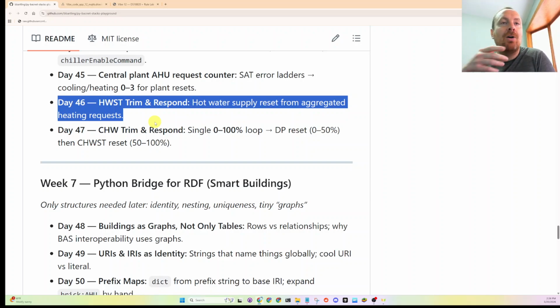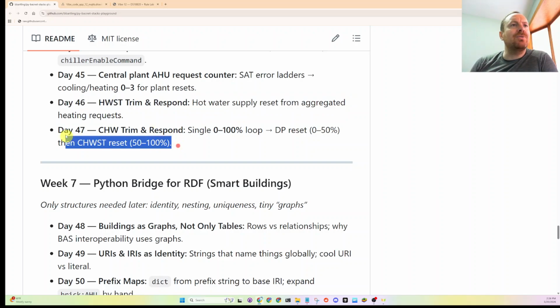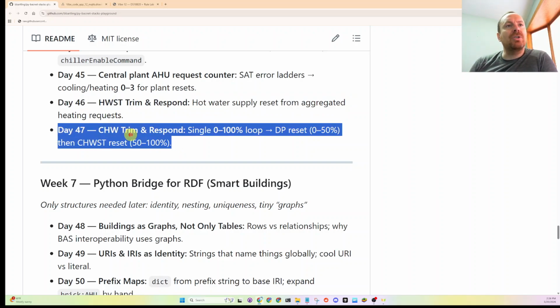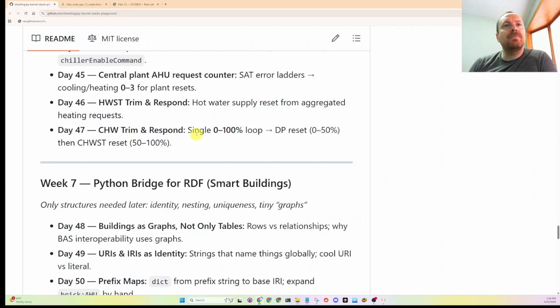And then I hope to get into the Guideline 36 chiller plant, basically resetting the pumping differential pressure and also the chilled water temperature set point. So yeah, pretty cool stuff here.